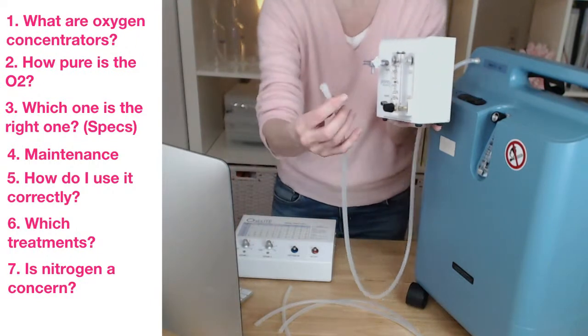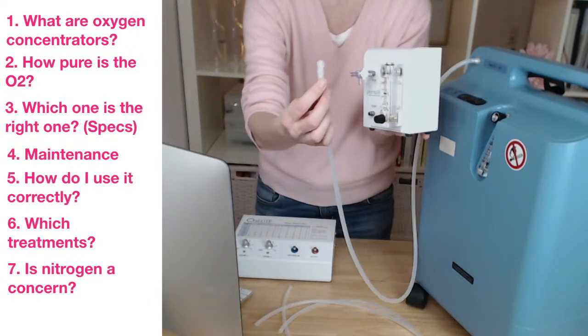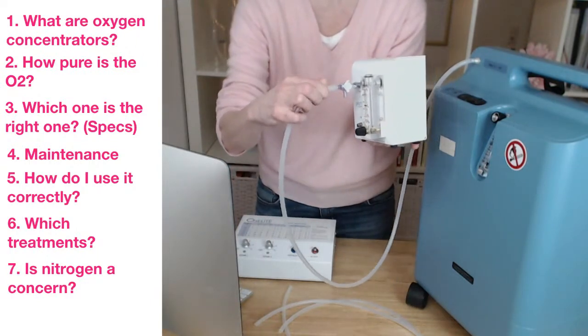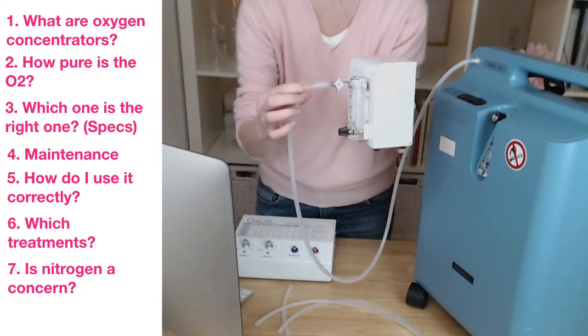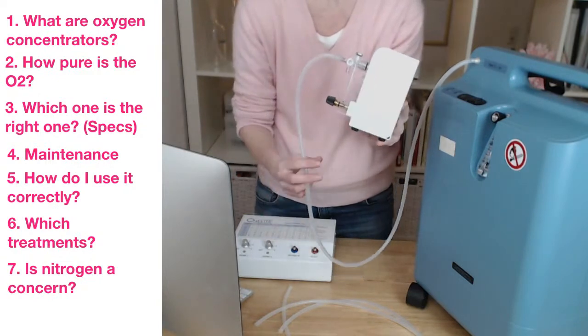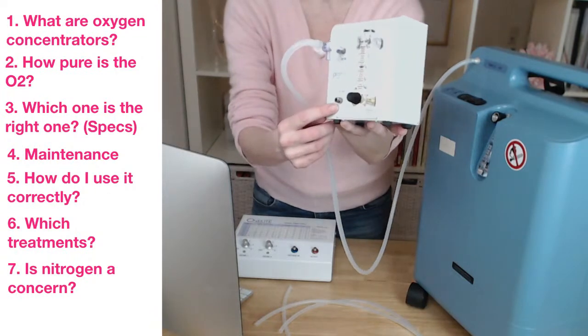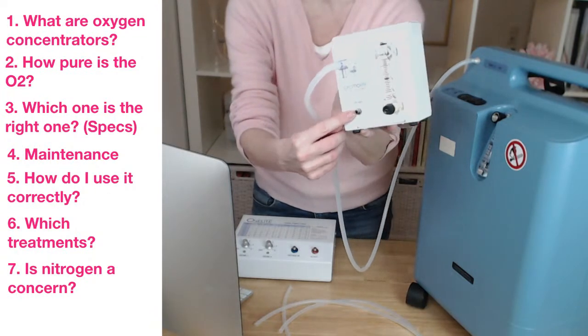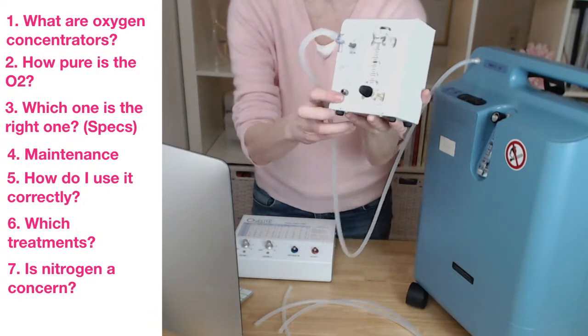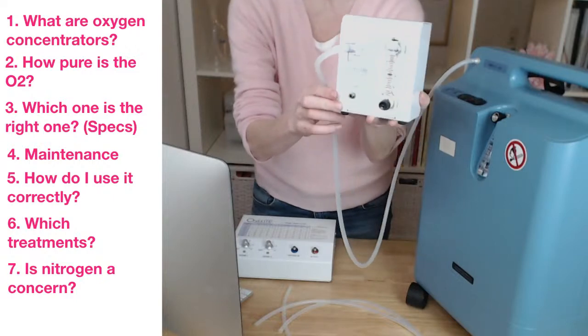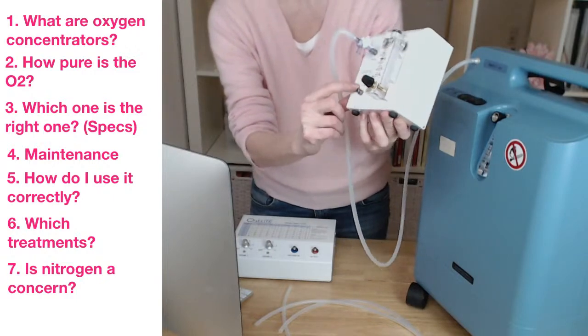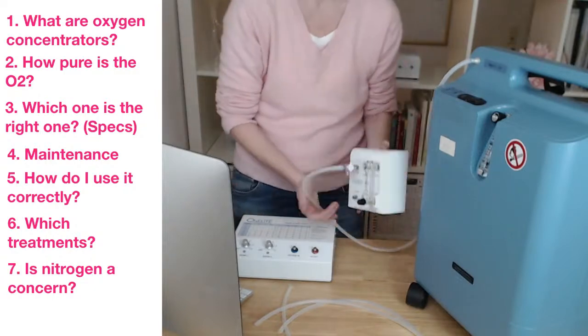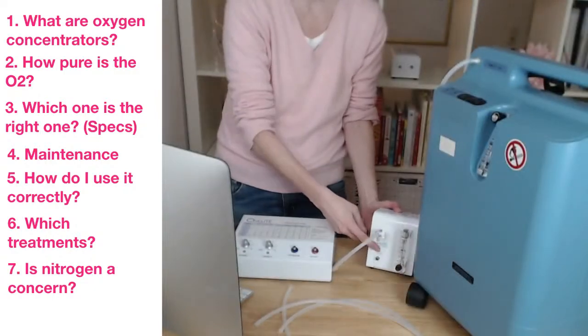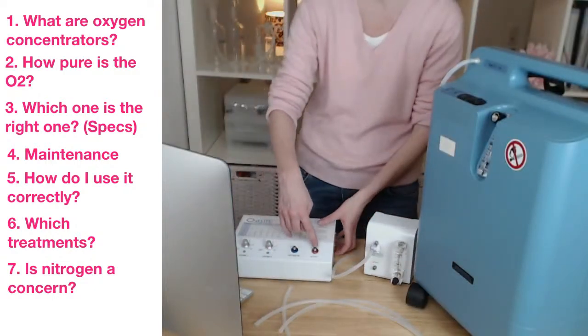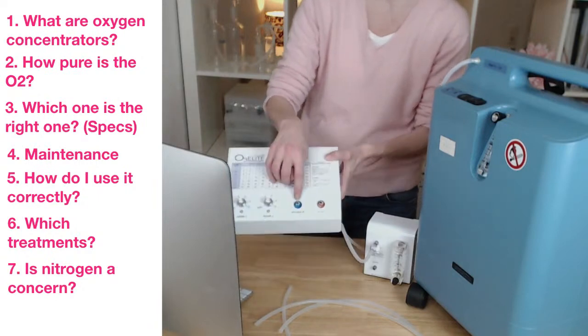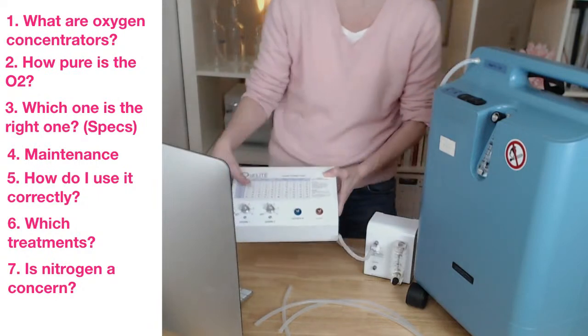So I take the Luer lock connector that I press into the silicone tubing, and I screw this into the oxygen in port. Okay, and here is an oxygen out port. I think there's too much light here for you to see this, but it says oxygen out. And now I need to connect the oxygen out with the oxygen input of my ozone generator.